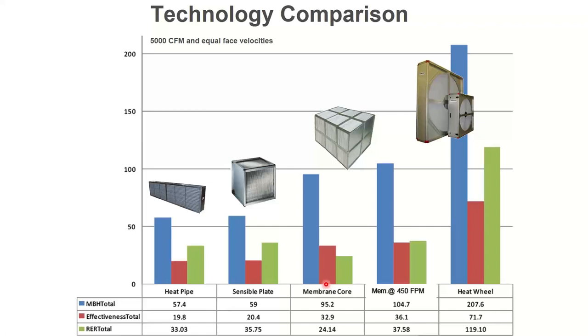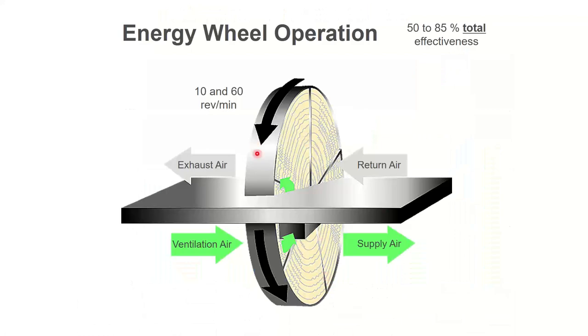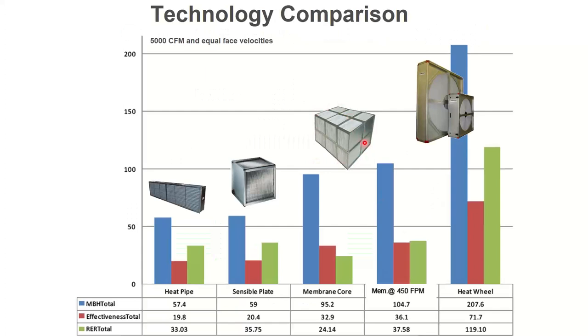You can do a significantly larger amount of BTUs in a given amount of space with a wheel versus the other technologies with the fixed plates. But sometimes you can't use the wheel. Because this wheel is in motion, there are some places where, from a code perspective, that's not going to be allowed. So sometimes, somewhere regulated by IDPH, which has a different annotation nowadays than it would normally, I'm talking about Department of Health facilities, like hospitals, those kinds of places, or toilet exhaust in the city of Chicago, and only in the city of Chicago. Everywhere else in the world, it's fine. But in the city of Chicago, toilet exhaust cannot go through a rotating media. So in those kinds of applications, you will have to use a fixed core.